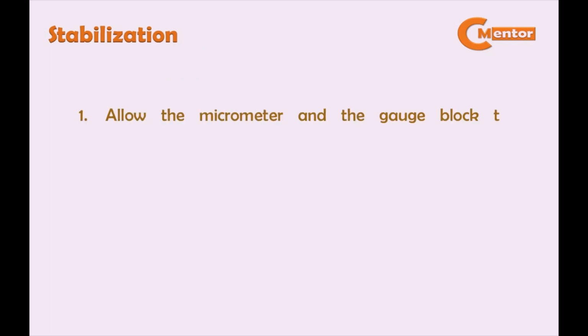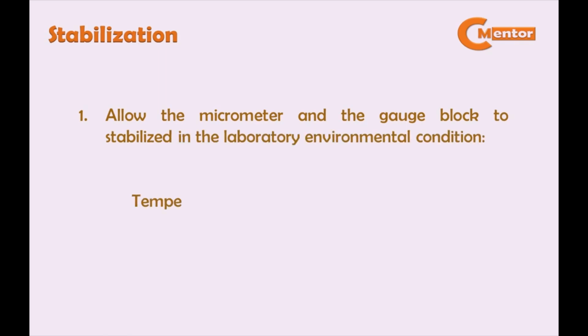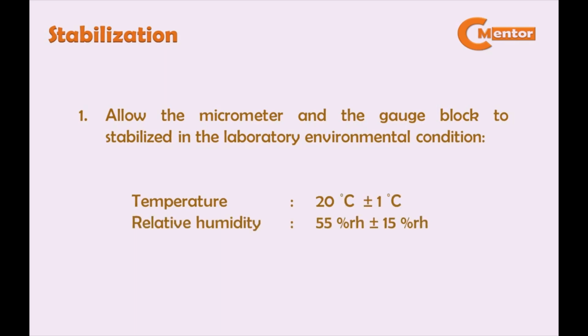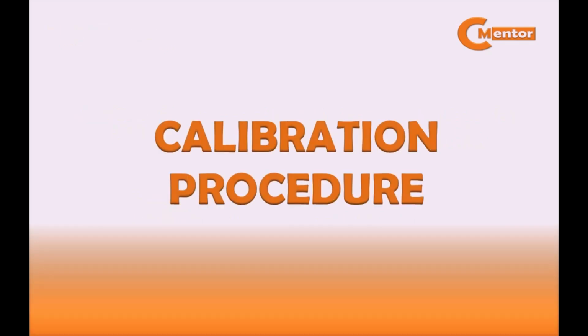After cleaning, stabilization must be performed prior to calibration. Allow the micrometer and the gauge block to stabilize in the laboratory environmental condition of temperature 20 degrees Celsius plus or minus 1 degree Celsius, and relative humidity 55% RH plus or minus 15% RH. This is to minimize the effect of thermal expansion of the gauge block that may contribute to the measurement during calibration. It is known that metals expand and contract at temperatures other than 20 degrees. Now we will proceed to the calibration procedure.